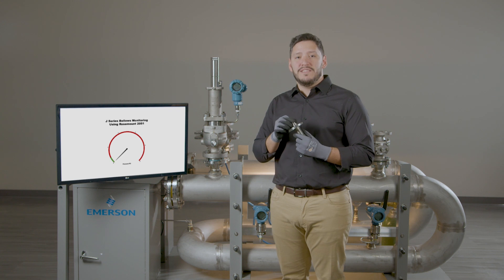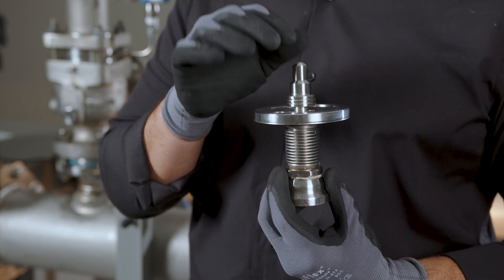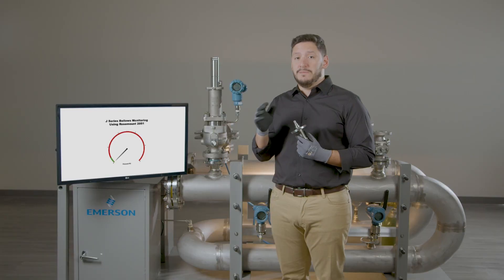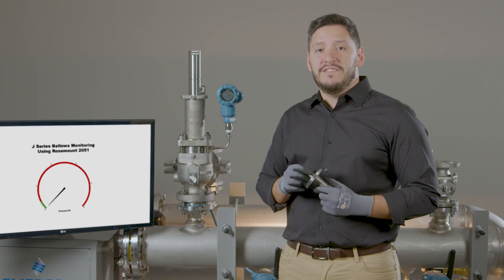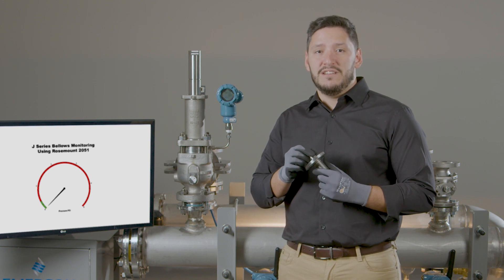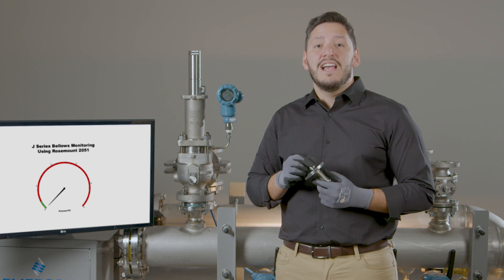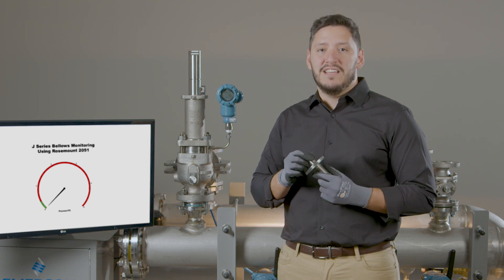The guiding clearances of the piston are held to a minimum with a machined labyrinth seal around the piston, reducing the flow between the piston and the adapter. In the event of a bellows failure, the seal minimizes any flow through the bonnet vent to atmosphere, reducing fugitive emissions significantly, as well as maintaining the balancing effect of the valve.